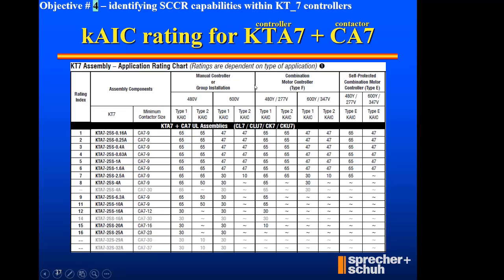So as we go through the column headings here, manual controller group installation in this first column, 480 volt delta versus combination. Now we're talking about type F and type E. But look under type F, now we're talking about type 1 and type 2. Well, doggone, what's the difference between type 1 and type 2? All right, I'll explain that in just a minute. But just reviewing the KAIC table for a KTA7 plus a contactor.